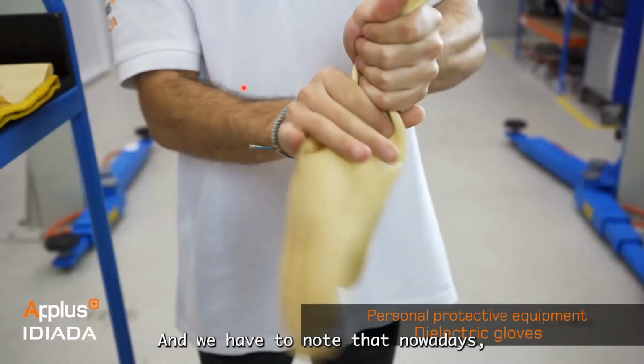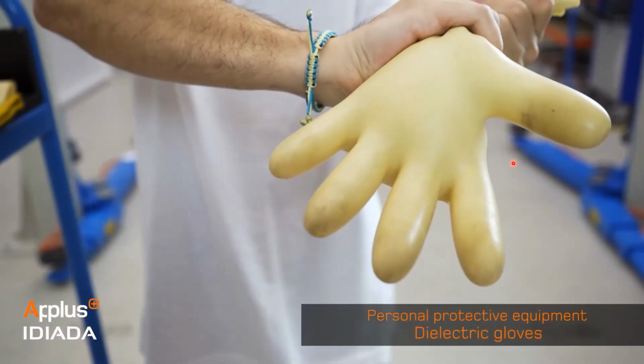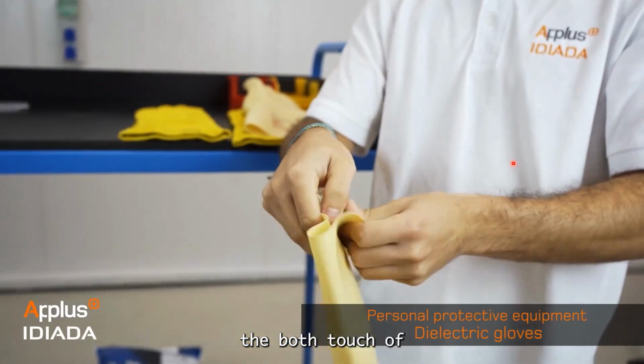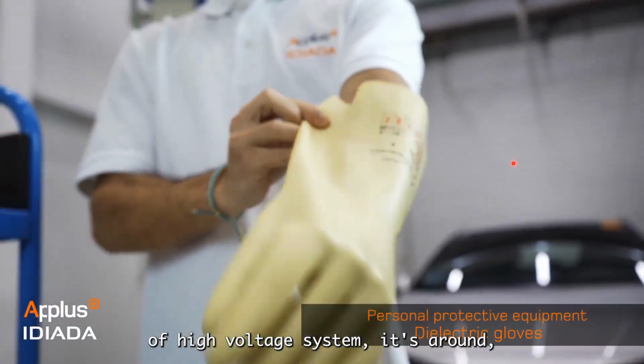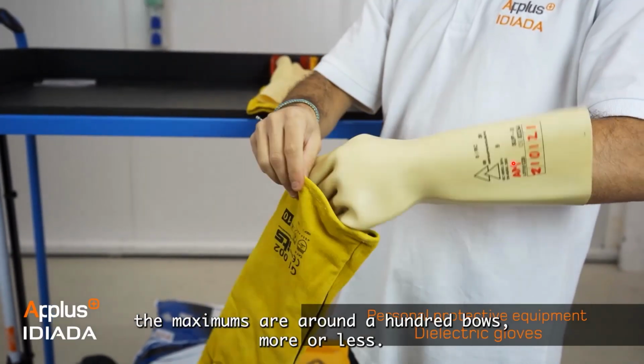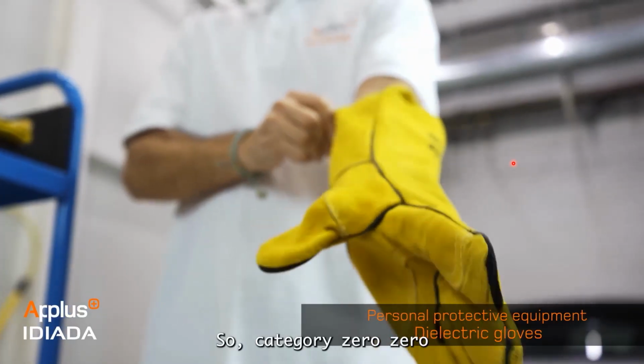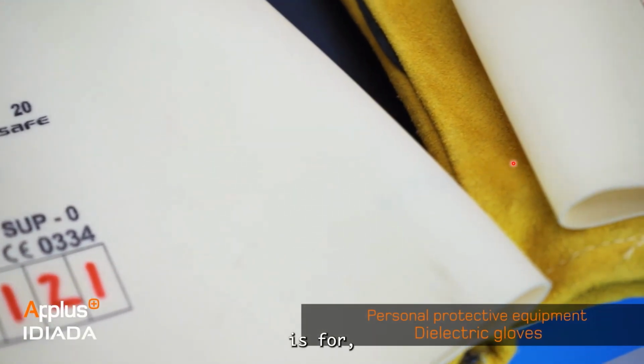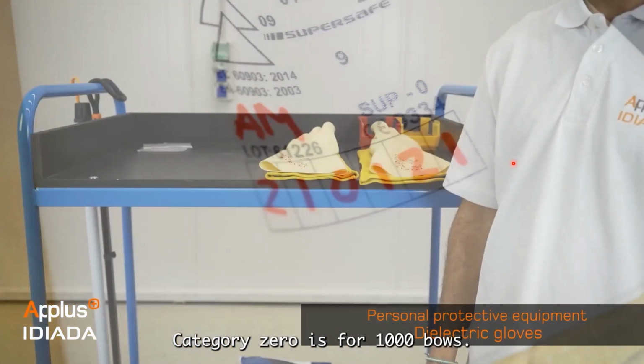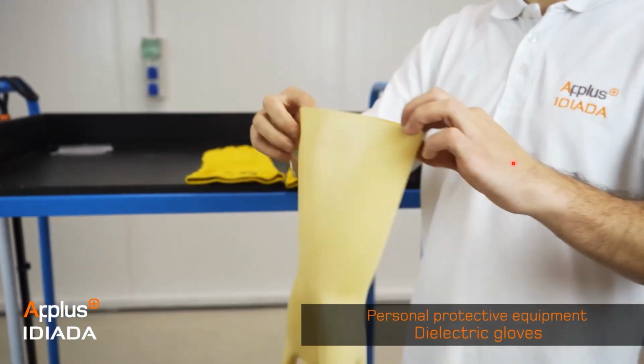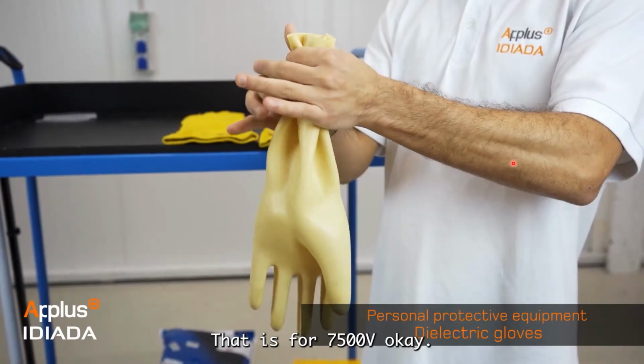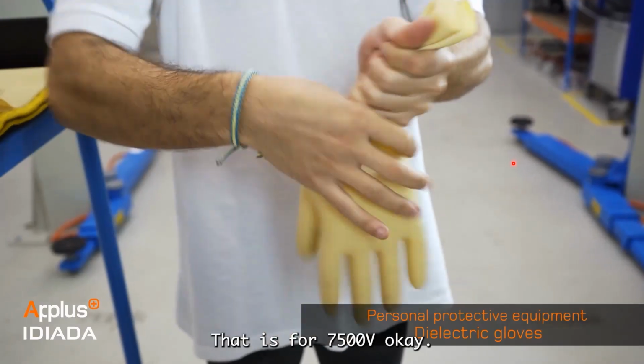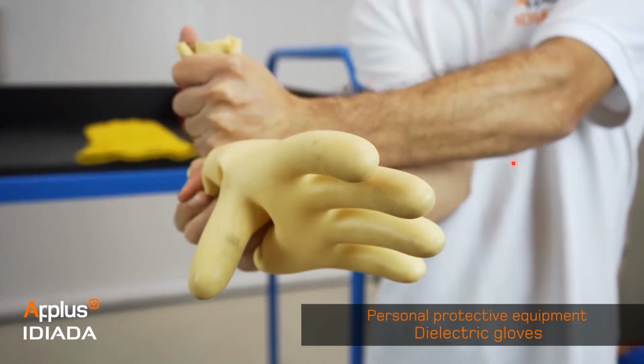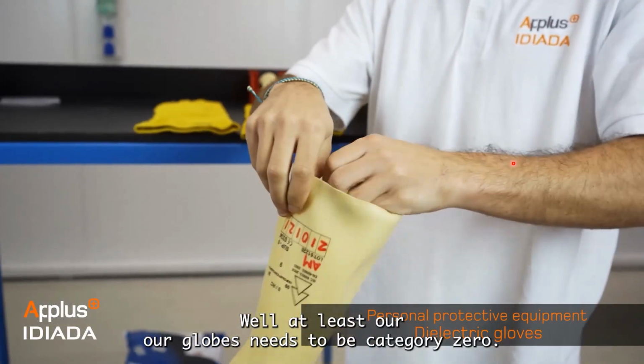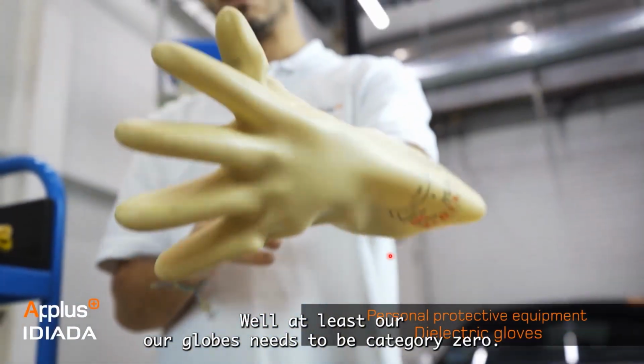First, we have to know that nowadays the voltage of high voltage systems is around a maximum of 800 volts or so. Category 00 is for 500 volts, category 0 is for 1000 volts, and category 1 is for 7500 volts. So which category do we need? Well, at least our gloves need to be category 0.